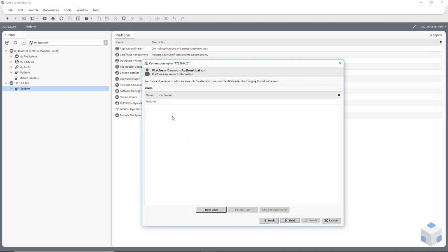So now I can add a new user if I want. Okay, so I've got two users now. You can add as many as you want here, because the heightened security now is to change the defaults. It's a good idea to have more than one user in case you forget the first one, or you don't want to give someone that first one, but the site's been handed over to someone else, and you have to give them a platform user or platform credentials. It's a good idea to have your company one, and then like a site one, you can give to someone else.